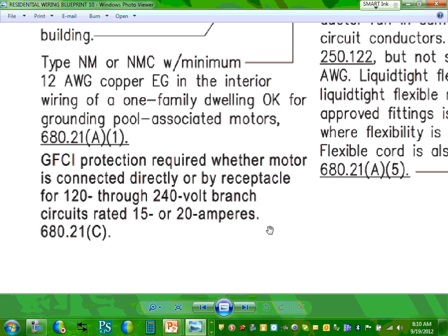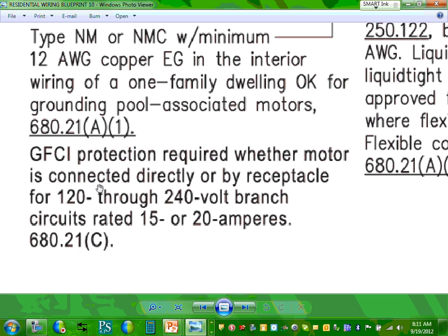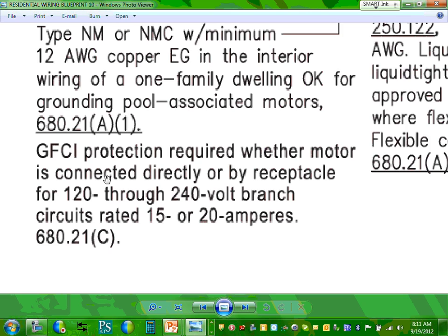Has to be GFCI. So what happens if it's hardwired? What do you do if it's hardwired? You put a GFCI circuit breaker, a 2-pole GFCI circuit breaker. Can I have thumbs up, Chad? For our swimming pool, since it's going to be 240, we're going to have a 2-pole GFCI circuit breaker protecting this circuit, because most likely it's going to be 20 amps or less. Can you guys highlight this particular one here? Because that applies directly to our project.